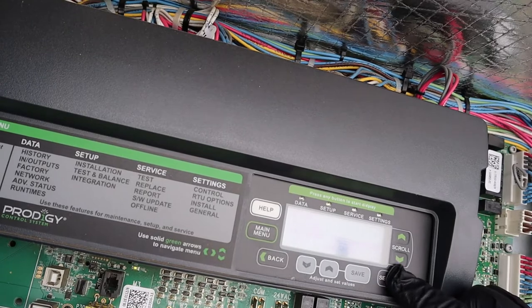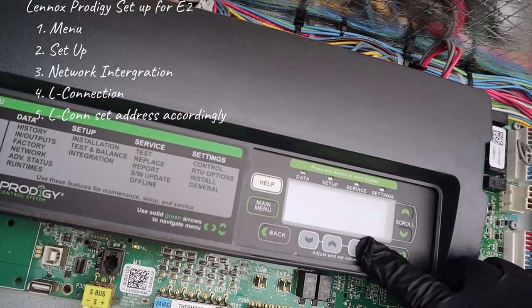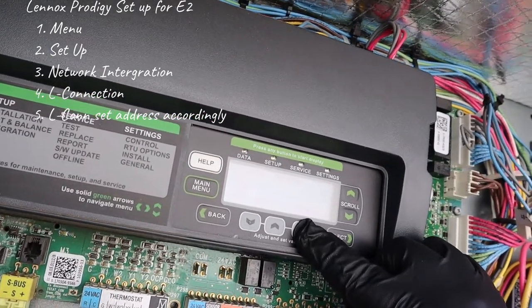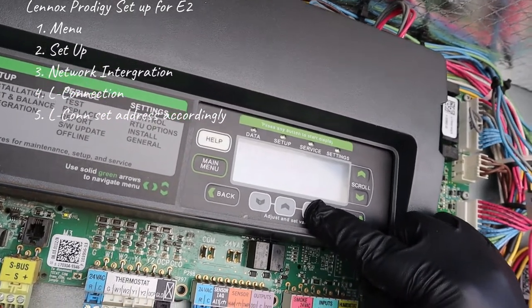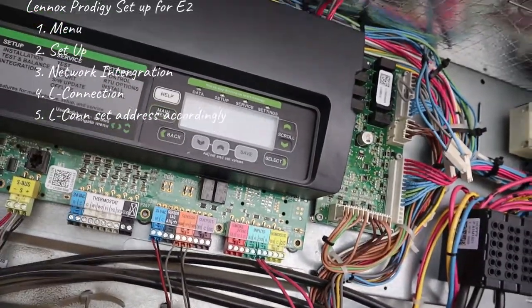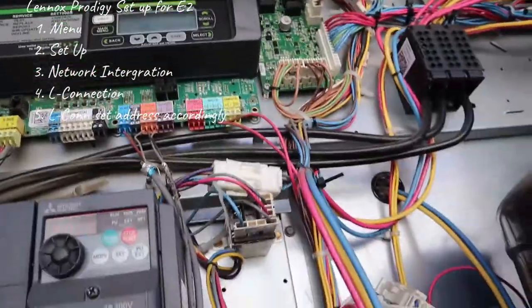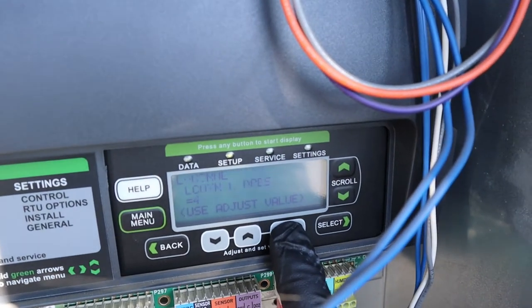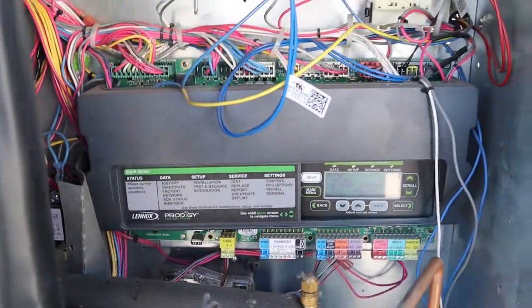For these Prodigy controllers when they're tied into the E2, they have to be set up in the network integration as L-connection, and then you put the L-con address to whatever you want to set it up to. You daisy-chain each Lennox unit to the E2 all the way back, making sure every unit is wired the same — positive to positive, negative to negative. Unit number four is addressed correctly.